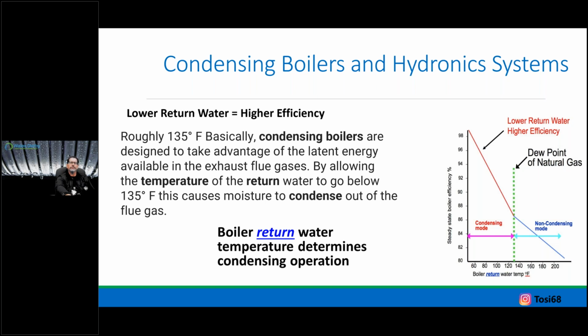Neat stuff here, right? So boiler return water temperature determines the condensation operation, right? It's all about what we do on the system side, the thing that's been there for the last 35 to 50 years. Take a good close look and do a heat loss there. See what we're dealing with. Is it fin tube? Is it radiant? Is it hydro coils? Panel rads. There's a list of emitters that we might have options with. It might be a mixed bag of stuff.